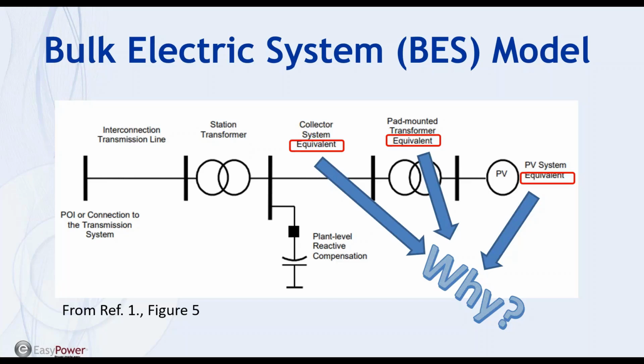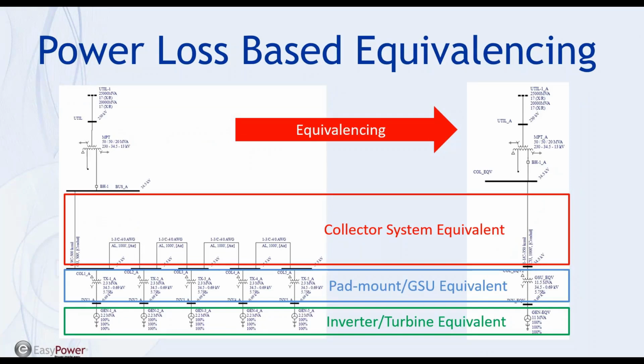That's my take on it. Now, how could we do that? By comparing the one line we have on the left-hand side and the equivalized model on the right-hand side, we know that we don't have to worry about the main power transformer. We just need to build an equivalized circuit for the collector system, pad mount or GSU, and inverter. So we call the collector system equivalent the equivalized collector system. And we have the pad mount equivalent, inverter equivalent, or generator equivalent. We will introduce procedural steps for each one of them.